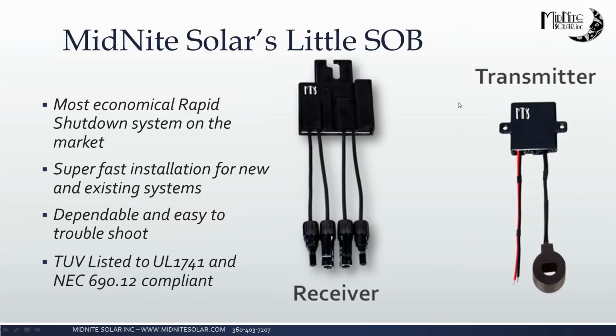And I assume, Sue, you want to take care of the SOBs for us, little SOBs? Sure. So this is our new rapid shutdown product. It's the most economical rapid shutdown on the market. It's very, very easy to install on new systems as well as retrofitting for older systems. It's a very dependable, fail-safe product. It does fail in the open mode, which does not allow power to come down from the panels, so it is very safe in that sense.